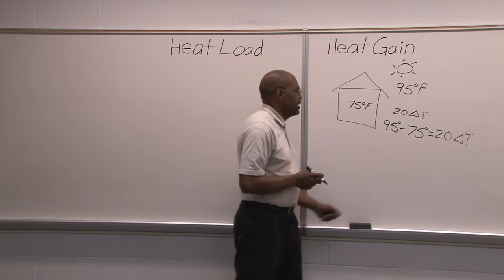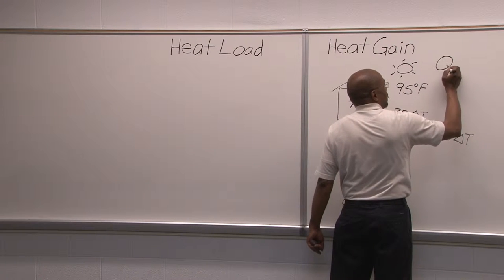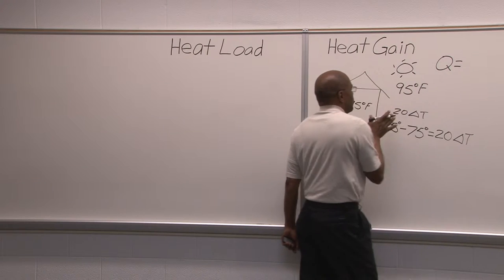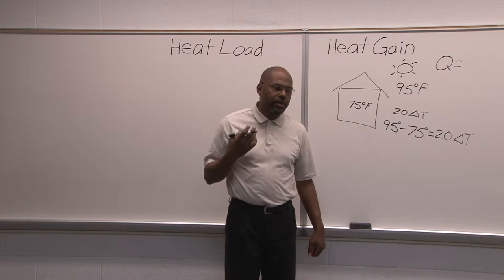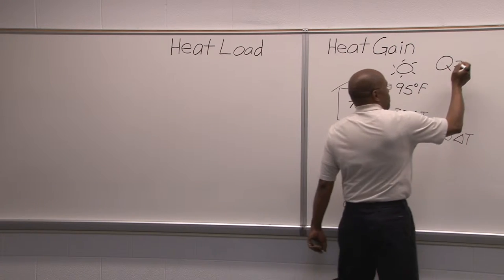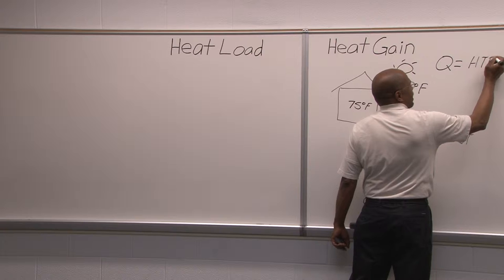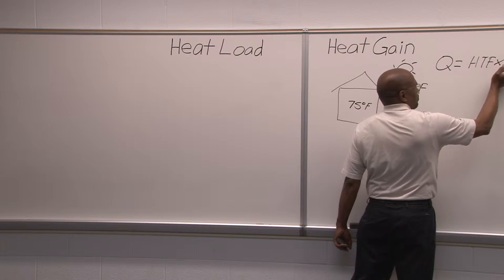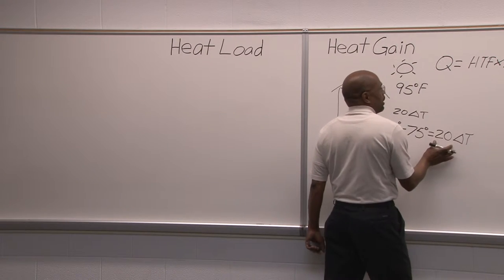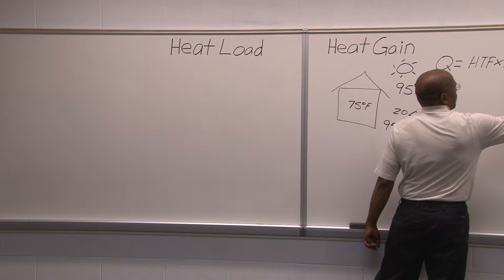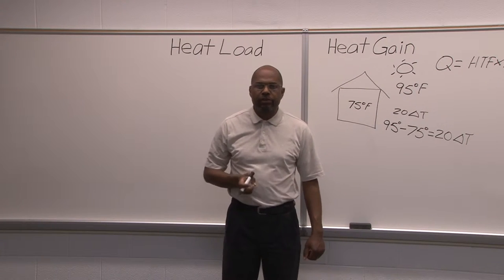Now, as we look at that, we add this to the formula of energy content — the quantity of energy based on the materials: the walls, the ceiling, the floors, the windows, the doors, all the components of a house. If we know the heat transfer factor times the area of the material times the delta T, we would know how much heat is transferring through it at that time.